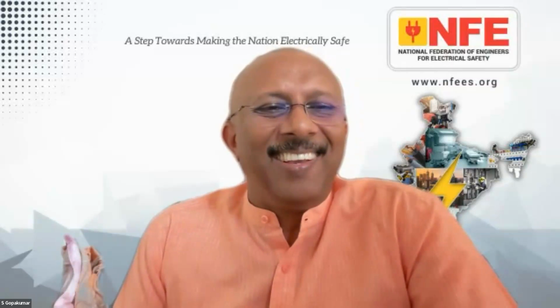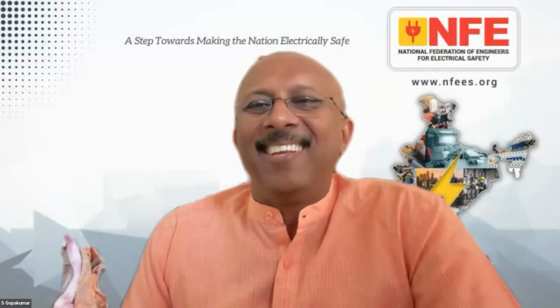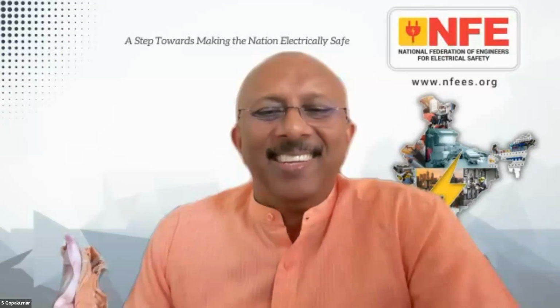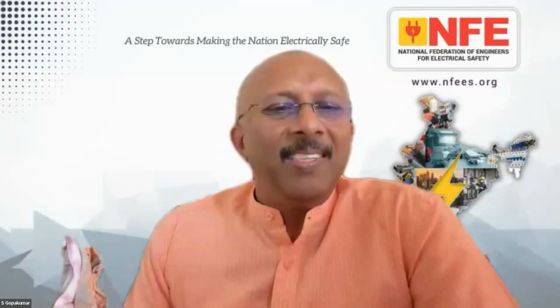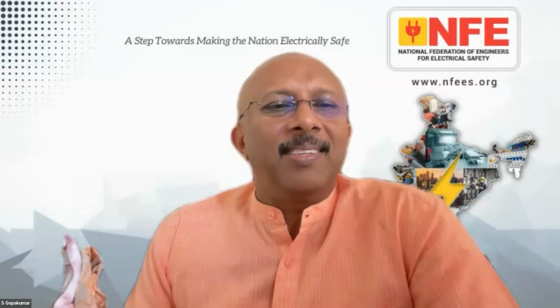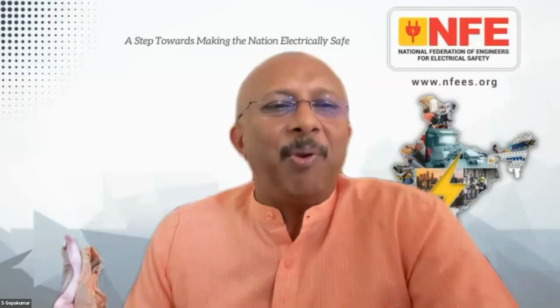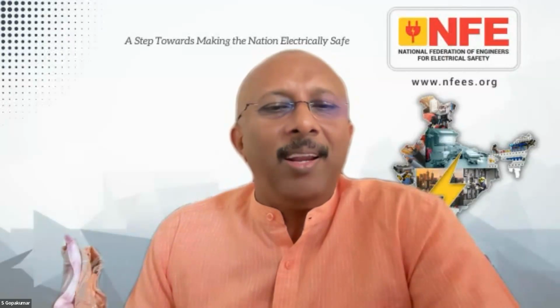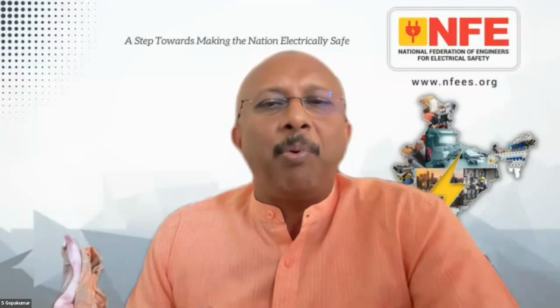That's what I wanted to clarify, that this should not be people using any other point which is isolated from the machine as an earth point. Earthing disease. Not good earthing disease. It is earthing disease, and this is very much prevalent in a lot of people. In my experience, this earthing disease is one of the main reasons for accidents, shock as well as fire, because we don't do it properly. We try to make it complicated. It's a simple subject. All metal parts, all dead metal parts must be interconnected in a proper, efficient way.